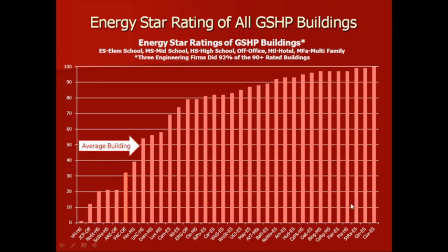And when we did the buildings, we did about 40 ground source heat pump buildings where we surveyed. We got water temperatures, loop temperatures, energy use, descriptions of the systems, and of course when you do the Energy Star rating, you have to get the occupancy and the number of students and number of occupants, the number of computers, and those sorts of things.